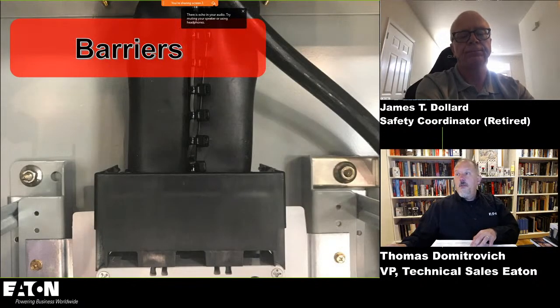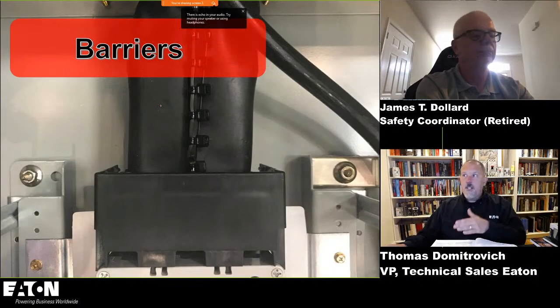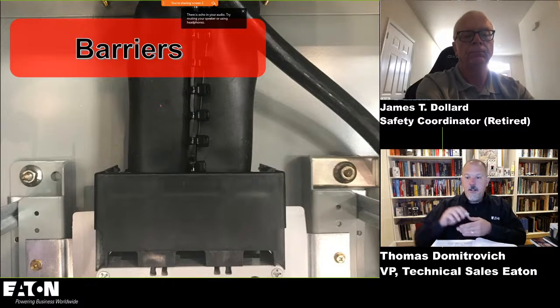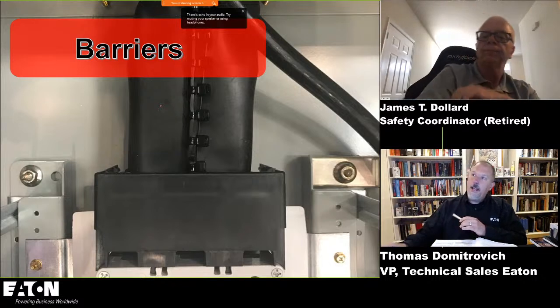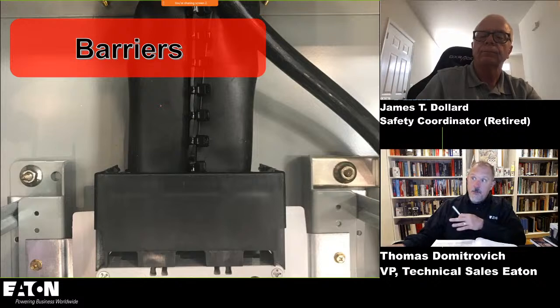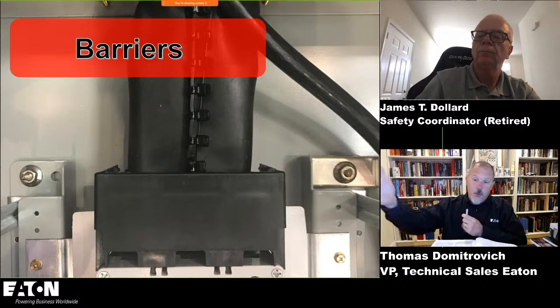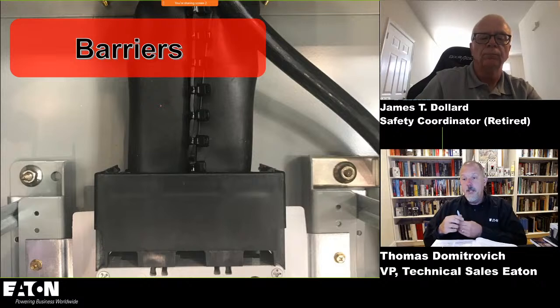All right. So the first level that we're going to talk about are barriers, and I see Don Ganir has had a question, and it directly relates to these requirements. His question is: do the barriers required on the line side of service equipment, which is what I'm showing on the screen here, eliminate the exposure to energized parts in service equipment? And that's a really good question.